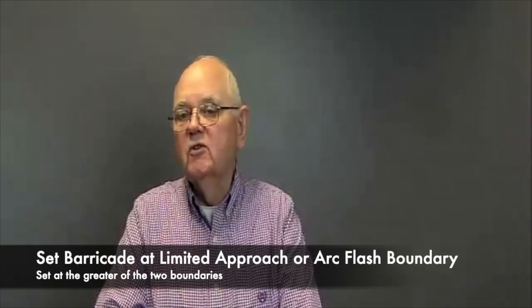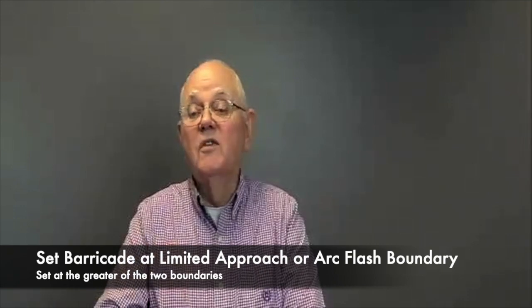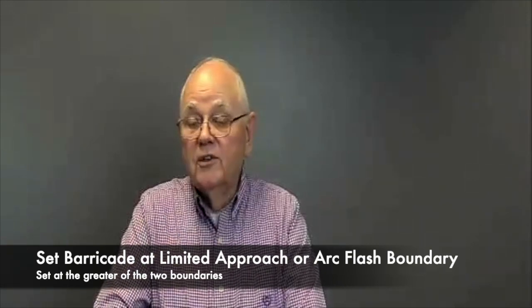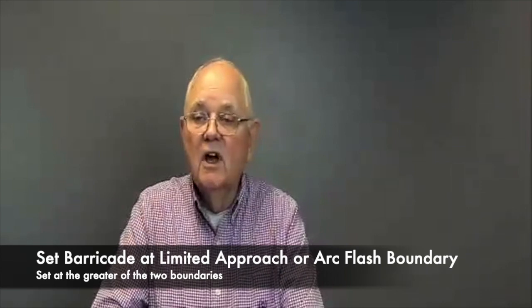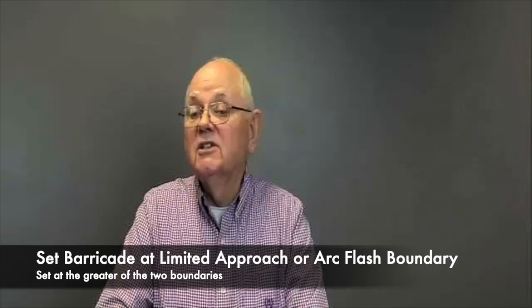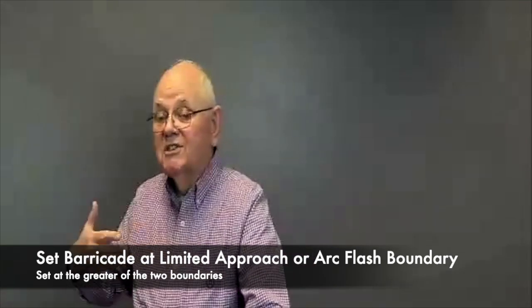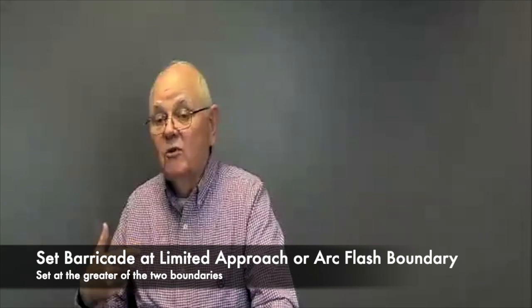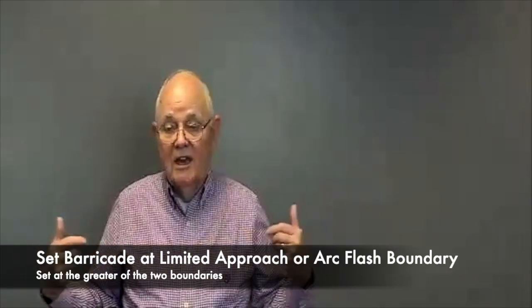When it comes to setting up our barricades, in other words, the physical obstruction to keep people away, we either want to set it at that limited approach boundary we mentioned earlier of at least 5 feet away for medium voltage where the conductor parts are fixed, or we want to set it at the arc flash boundary. Whichever of those two distances is greater is obviously where we want to set the physical barricade so that people do not get injured.